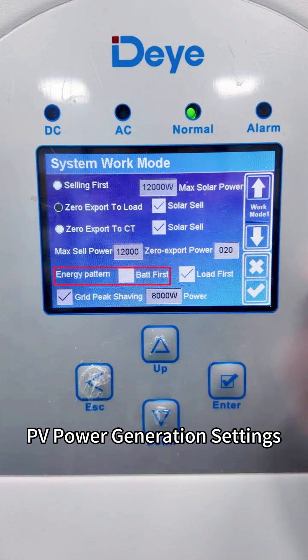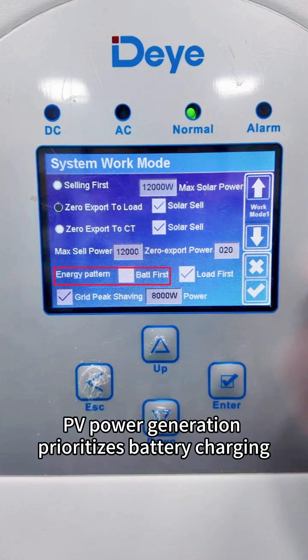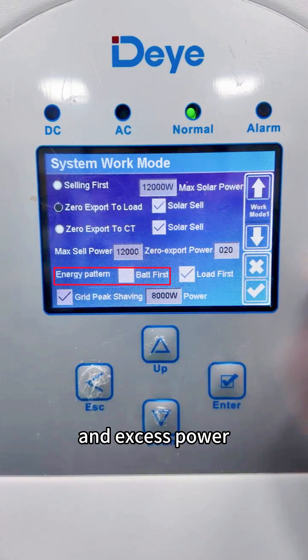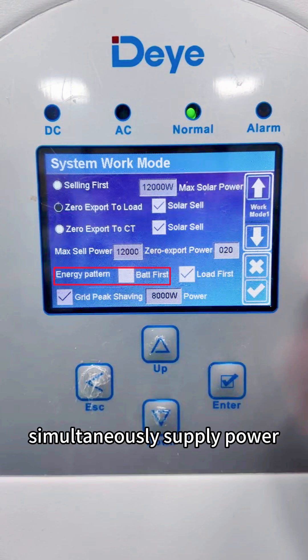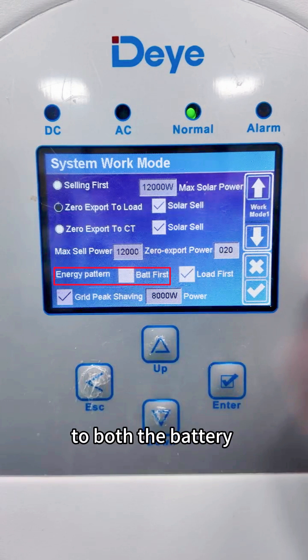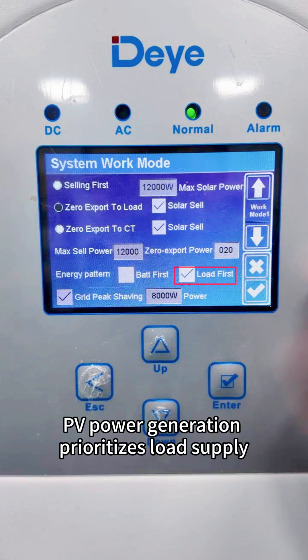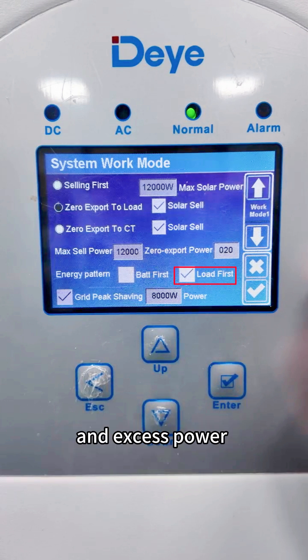PV power generation settings: PV power generation prioritizes battery charging, and excess power is supplied to loads. If PV power is insufficient, the grid will simultaneously supply power to both the battery and the loads. PV power generation can also prioritize load supply, with excess power charging the battery.